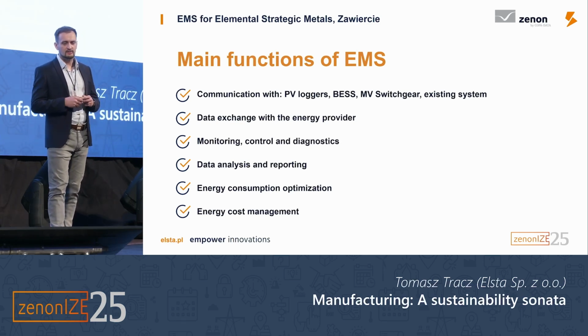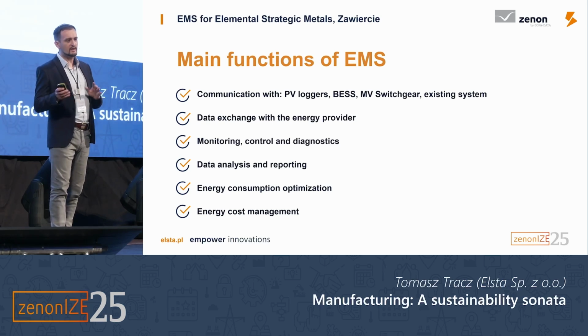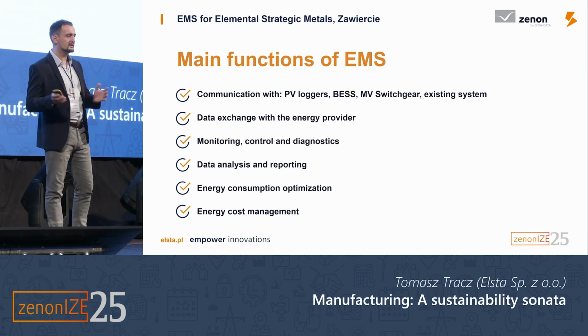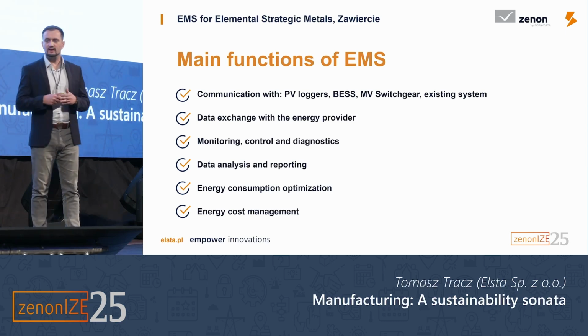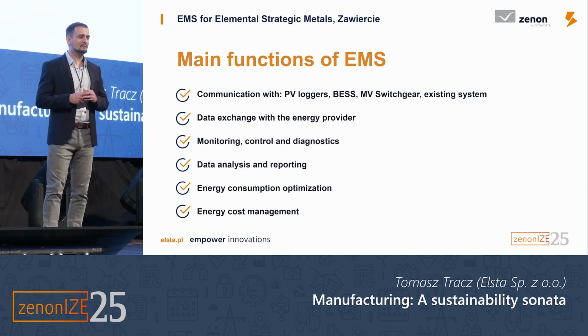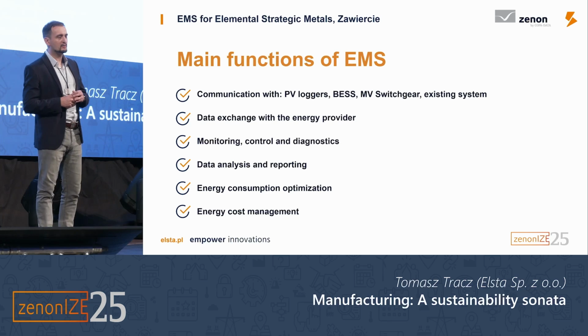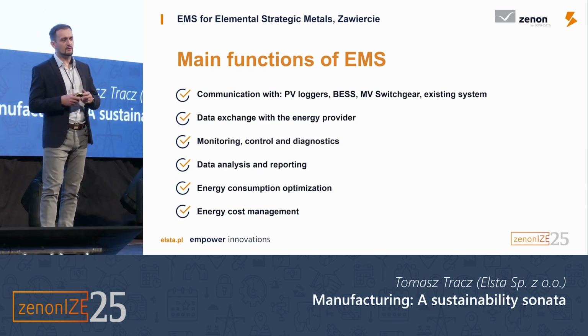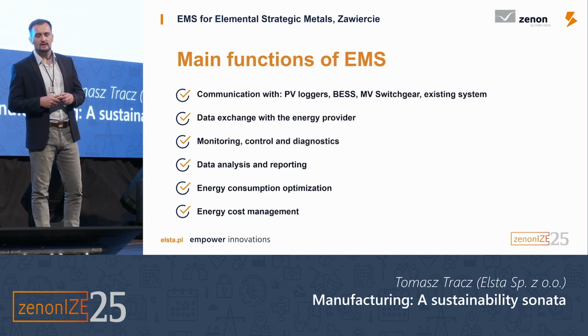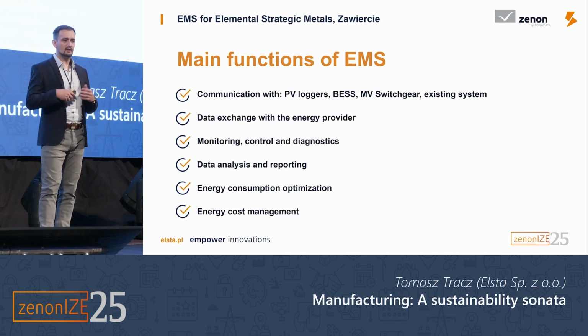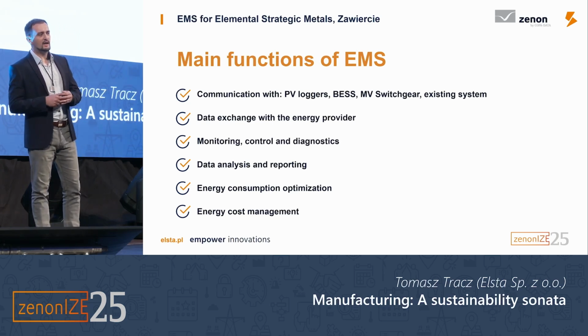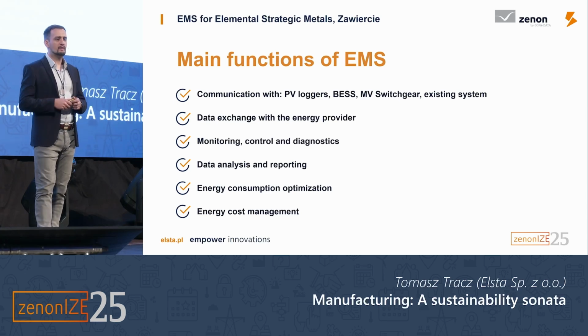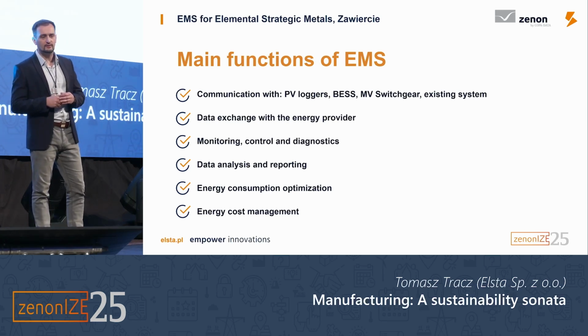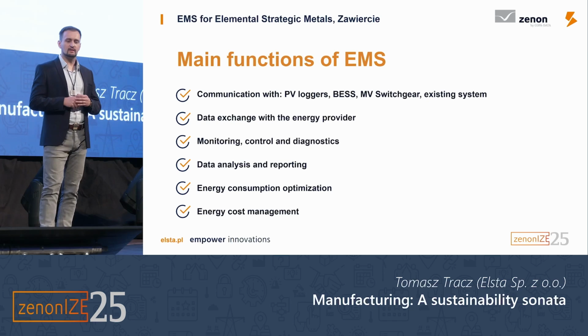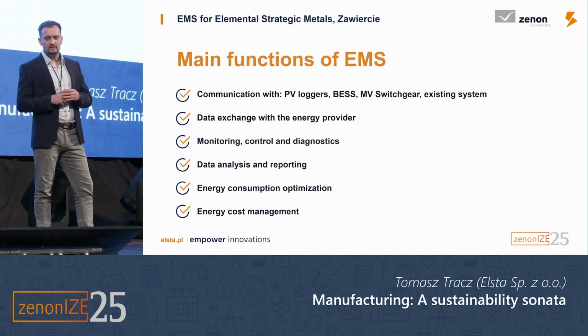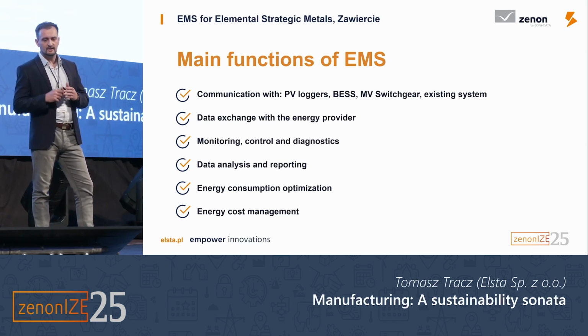This is, I would say, a shortcut, because EMS is not contacting directly all of these devices. I would like to say that we are an SCADA application already, but we had to put in some hardware and we utilized the RTU to exchange the information together, to change the protocols. So Zenon is more for acquiring this data. We put some algorithm above the Zenon due to its functionality for extensions. We could put even C# algorithms over it.